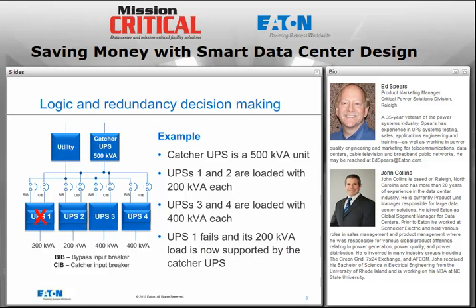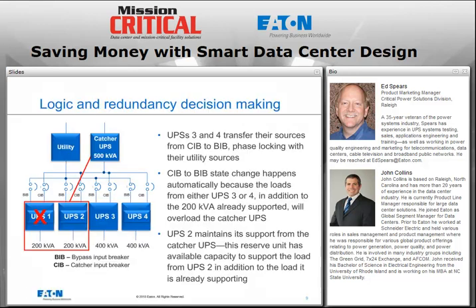On the other hand, if UPS 3 or UPS 4 were to subsequently fail, I would overload the catcher and I would want those UPSs to be fed from the utility. And that's exactly what happens. In the scenario that you see on this screen, if UPS 1 suffers a failure, the CIB breaker on UPS 1 remains closed because the catcher has capacity to support it and its load, but the BIB breakers would automatically close on UPS 3 and 4, making sure that the utility bypass is available to those UPSs should they have a problem. So in this case, we show UPS 1 suffering a failure and, of course, supported by the catcher UPS. Let's look at what happens next.